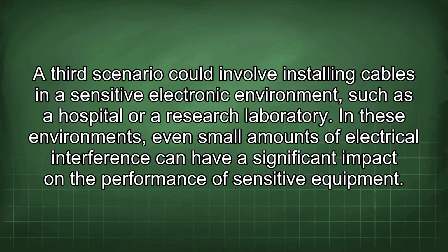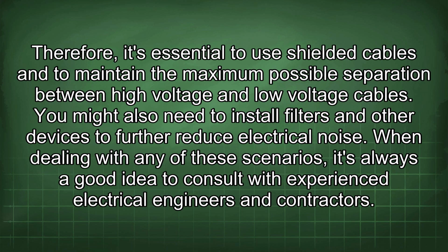A third scenario could involve installing cables in a sensitive electronic environment, such as a hospital or research laboratory. In these environments, even small amounts of electrical interference can have a significant impact on the performance of sensitive equipment. Therefore, it's essential to use shielded cables and to maintain the maximum possible separation between high voltage and low voltage cables. You might also need to install filters and other devices to further reduce electrical noise.